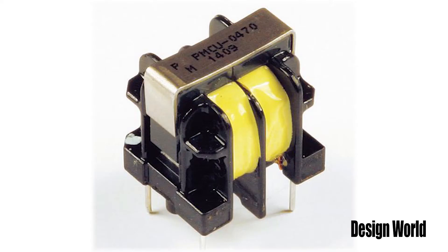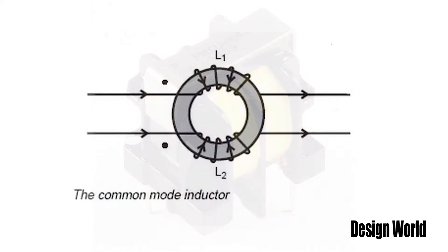The way you usually suppress common mode noise is to install some kind of filter on both lines conducting the noise. One kind of filter you can use is called a common mode choke. It's basically a choke or inductor containing two identical windings.